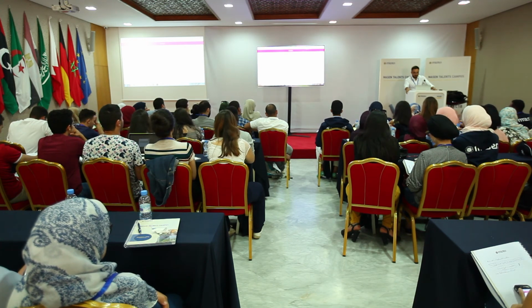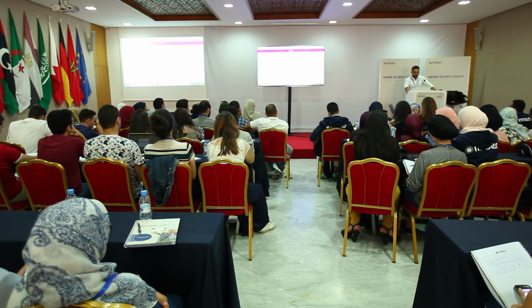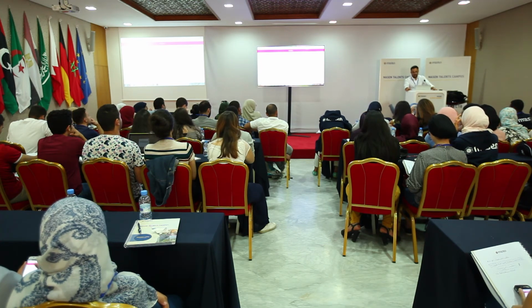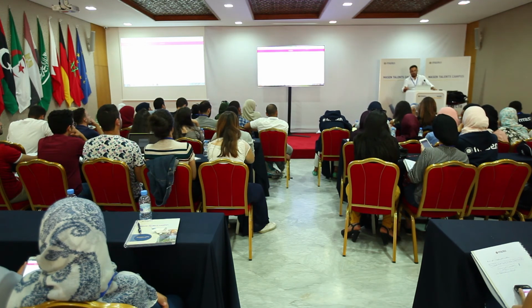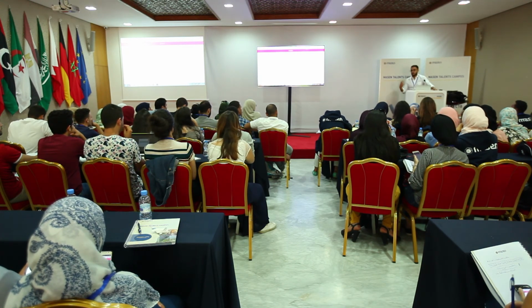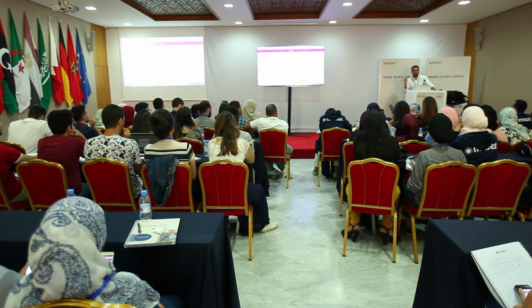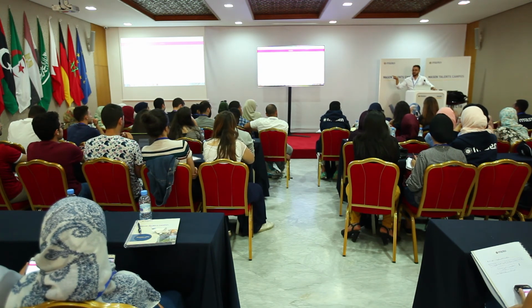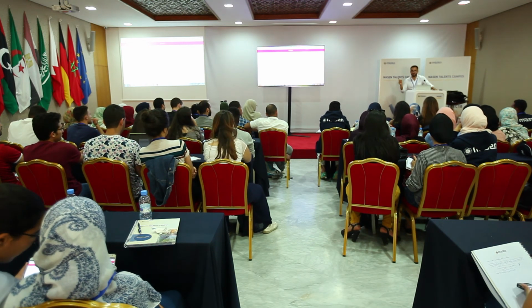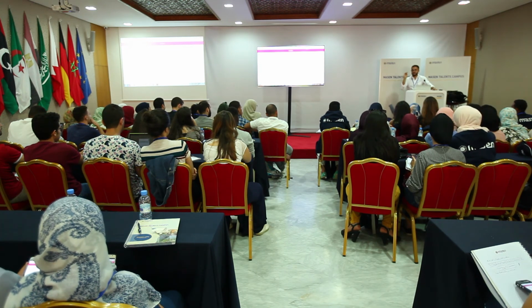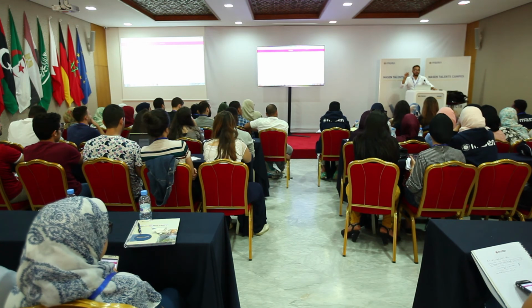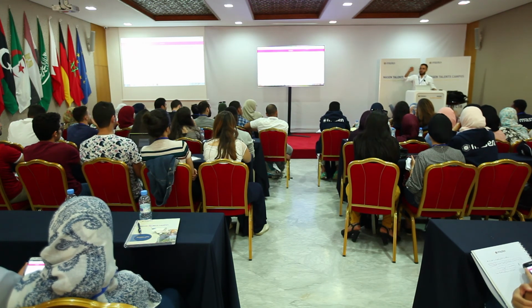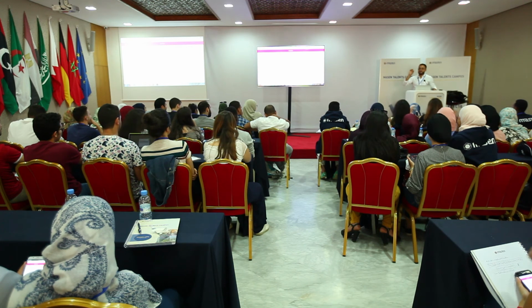If you're paid in a scheme like this, during daytime from, let's say, 8 a.m. till 5 p.m., you are paid 100, dirham per megawatt hour, whatever. Then from 5 to 10 p.m., you are paid 300. And from 10 p.m. till 8 a.m. the next day, you're paid 0. Of course, you're not going to build a power plant that provides energy 24 hours, because why would you sell electricity when you're paid 0? So the way these price schemes are set up defines in one way or another what the power plant will look like. The optimum plant for that example ends up with a small amount of hours of storage, because it will only sell when you're paid so much.